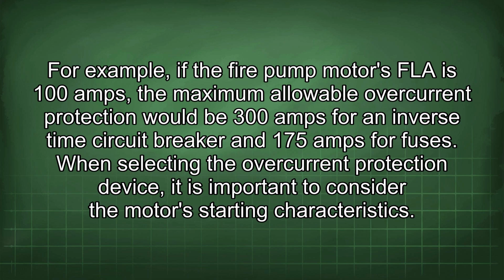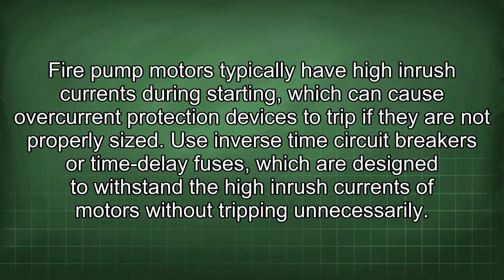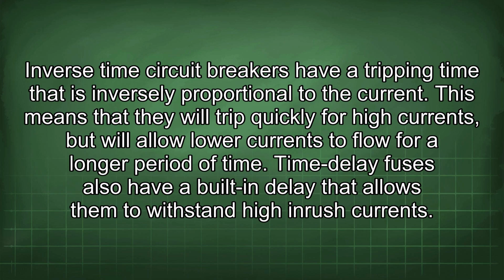When selecting the overcurrent protection device, it is important to consider the motor's starting characteristics. Fire pump motors typically have high inrush currents during starting, which can cause overcurrent protection devices to trip if they are not properly sized. Use inverse time circuit breakers or time delay fuses, which are designed to withstand the high inrush currents of motors without tripping unnecessarily. Inverse time circuit breakers have a tripping time that is inversely proportional to the current. This means that they will trip quickly for high currents, but will allow lower currents to flow for a longer period of time. Time delay fuses also have a built-in delay that allows them to withstand high inrush currents.